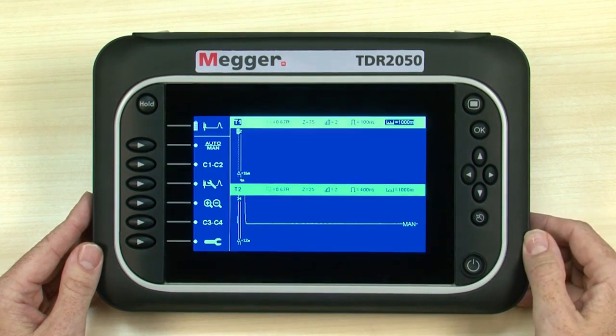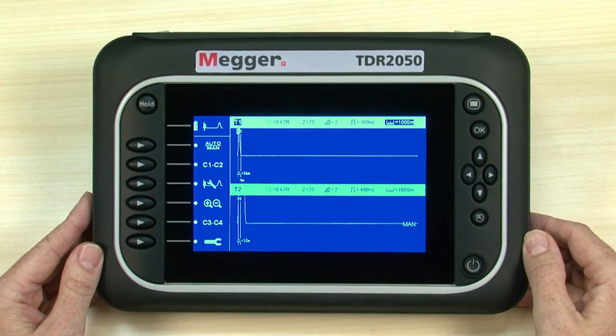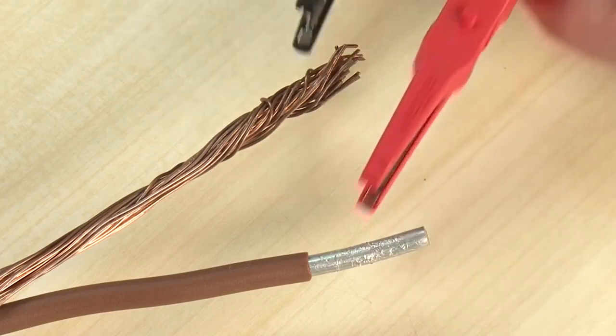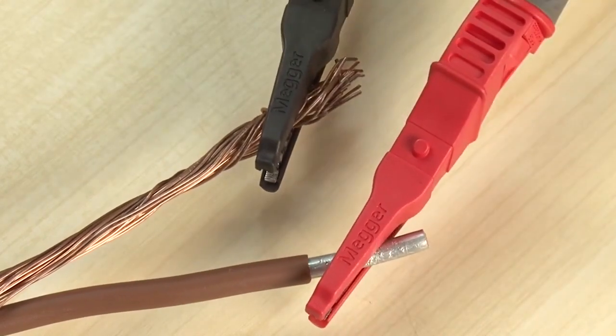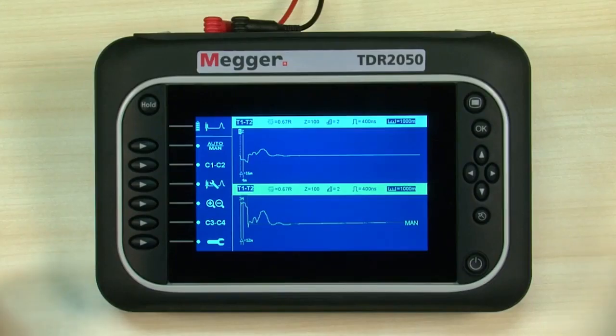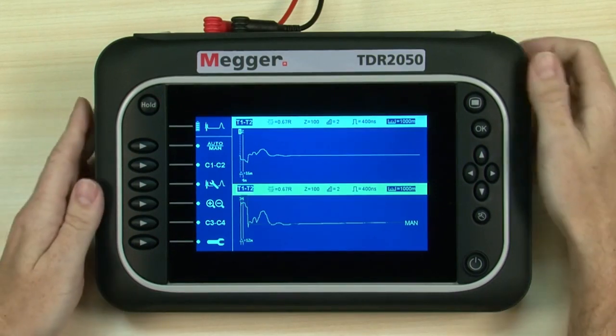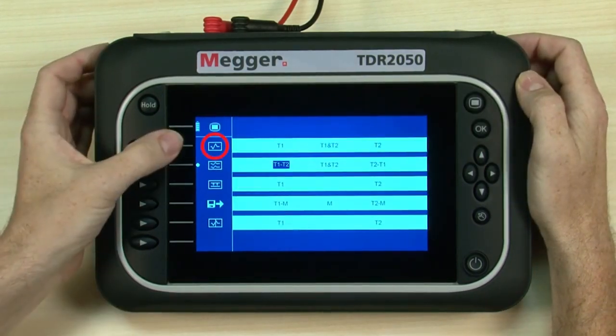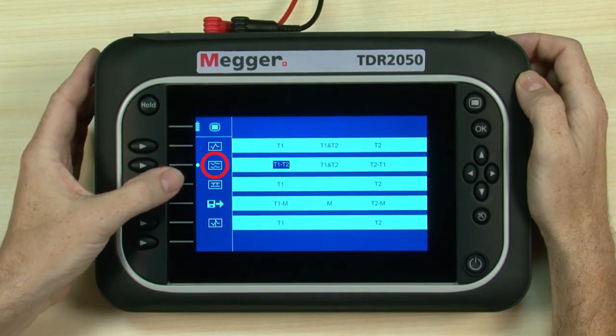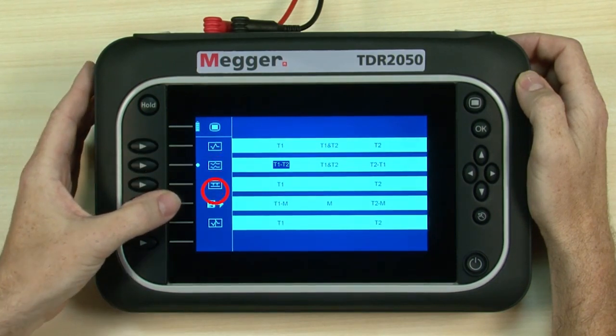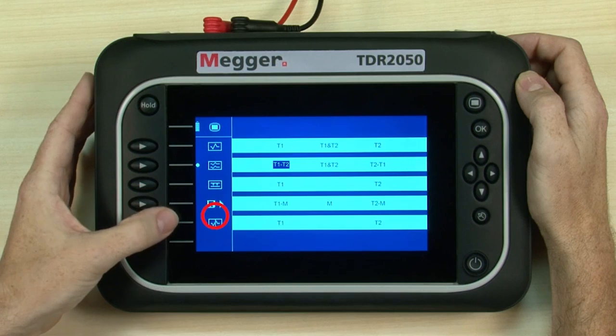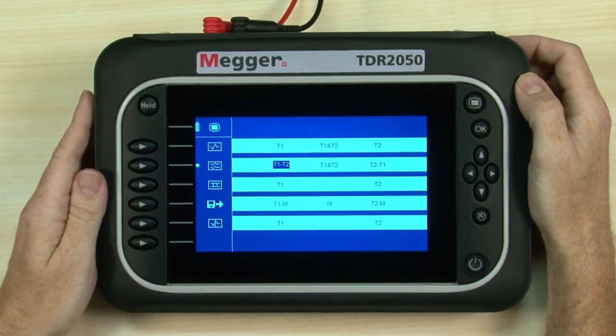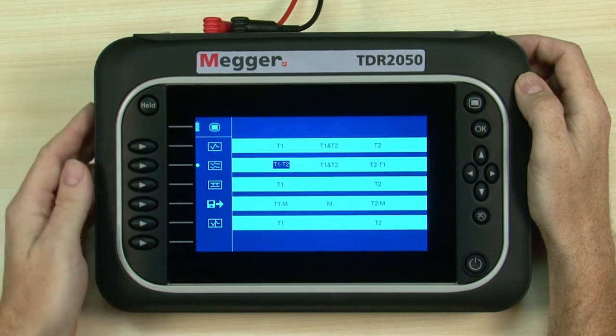Note the large high-definition colour display. Next we insert the test leads, and then we connect to the cable we want to test. Now we select the right mode for our test using the mode button. Here we can choose modes for full screen or split screen, and we can examine crosstalk, view memorised traces or set up for an intermittent fault test. We have a single cable to test, so we'll choose a single input mode.